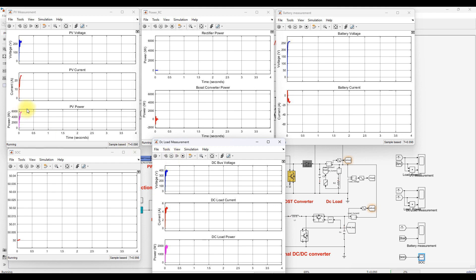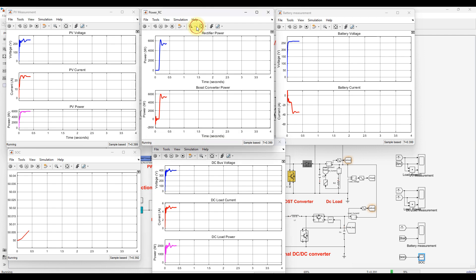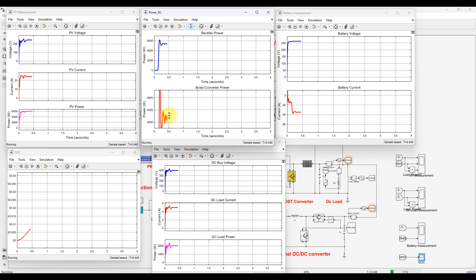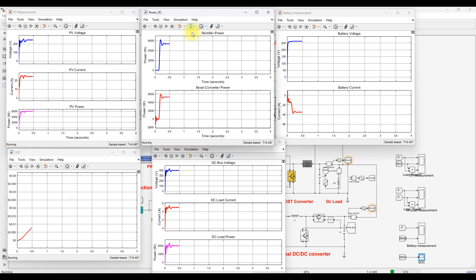During the initial condition at 1000 watts per meter squared, we are getting around 6 kilowatts from the PV array. At the boost converter stage, the output is around 5300 watts. The voltage is around 245 volts and the current is around 24 amps, giving around 6 kilowatts at 1000 watts per meter squared.